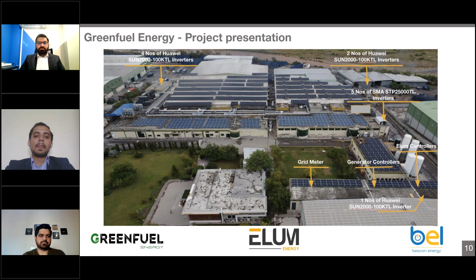The second issue was the distance, which was actually the major parameter and hindrance in executing this project, because there are different inverter sheds scattered across the plant. If we had gone with RS485 twisted pair Cat6 cable, the minimum distance between these sheds was more than 300 meters, and some sheds were even more than that. So these were the two main challenges we dealt with on this project.